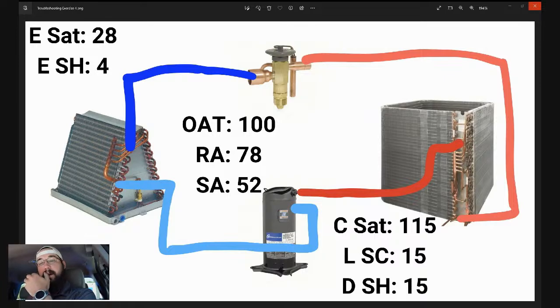Okay, let's chase that. So we're thinking that maybe we have a damper issue. Maybe the balancing dampers were closed. Maybe one of them got shut at some point. So that's a good check, we need to do that. So you walk around the supply and you look at all your balancing dampers. Everything looks to be open. Nothing is significantly restricted. If any of them are closed at all, it's just slightly.